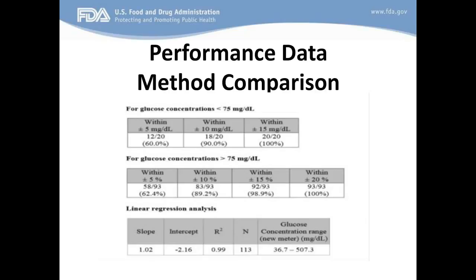So for glucose meters in this case, these are all things that one would consider under analytical validity. You have a well-defined analyte, and you're looking to see what the accuracy, the bias, and the precision are. Furthermore, we look to see what other things. Typically for glucose meters, we make sure that the values are still accurate at different altitudes. There is an oxygen dependence in some of these meters, so you want to make sure that if they're going to be used at a place with high altitude, they still give you accurate results. We look at interferences as the hematocrit changes. That is usually well known. And there are other substances that may affect the glucose meter, so we make the manufacturers evaluate them.